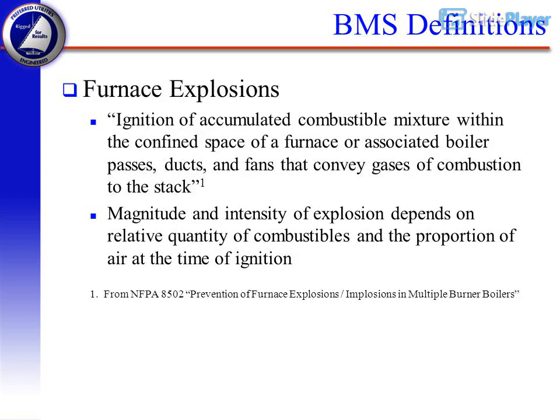BMS definitions. Furnace explosions. Ignition of accumulated combustible mixture within the confined space of a furnace or associated boiler passes, ducts, and fans that convey gases of combustion to the stack. Magnitude and intensity of explosion depends on relative quantity of combustibles and the proportion of air at the time of ignition. From NFPA 8502 Prevention of Furnace Explosions, Implosions in Multiple Burner Boilers.